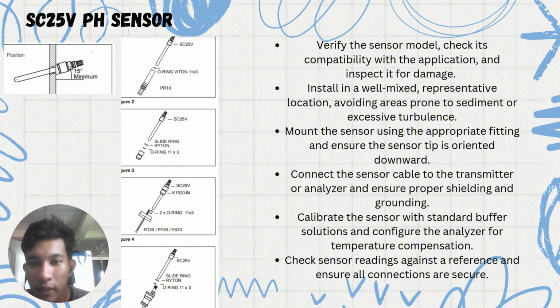This is the installation of the SC25V pH sensor. It takes a few steps to install it. The first point is to verify the sensor model, check its compatibility with the application and inspect it for damage. Number 2, install in a well-mixed representative location, avoiding areas prone to sediment or excessive turbulence. Number 3, mount the sensor using the appropriate fitting and ensure the sensor tip is oriented downwards. Number 4, connect the sensor cable to the transmitter or analyzer, ensuring proper shielding and grounding. Number 5, calibrate the sensor with standard buffer solution and configure the analyzer for temperature compensation. And lastly, check the sensor reading against a reference and ensure all connections are secure.